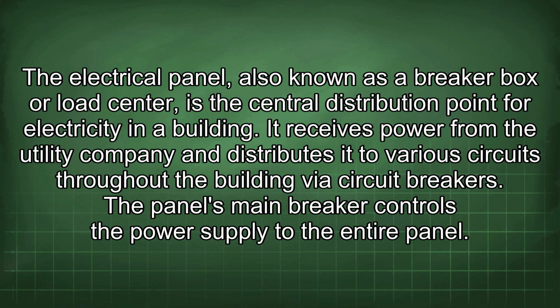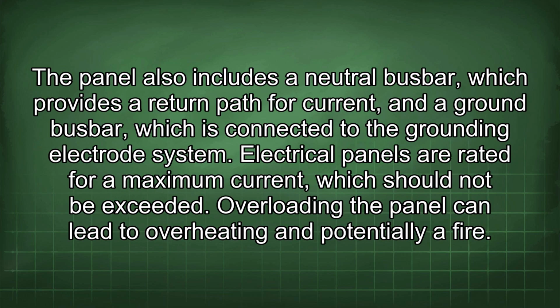The electrical panel, also known as a breaker box or load center, is the central distribution point for electricity in a building. It receives power from the utility company and distributes it to various circuits throughout the building via circuit breakers. The panel's main breaker controls the power supply to the entire panel. The panel also includes a neutral busbar, which provides a return path for current, and a ground busbar, which is connected to the grounding electrode system.